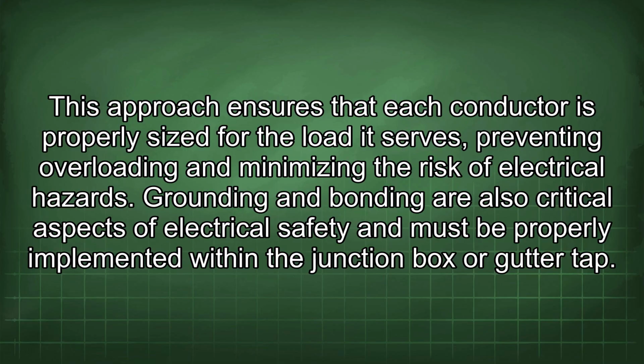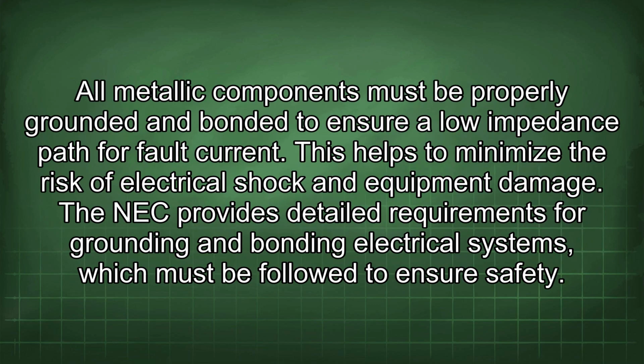Grounding and bonding are also critical aspects of electrical safety and must be properly implemented within the junction box or gutter tap. All metallic components must be properly grounded and bonded to ensure a low impedance path for fault current. This helps to minimize the risk of electrical shock and equipment damage. The NEC provides detailed requirements for grounding and bonding electrical systems, which must be followed to ensure safety.